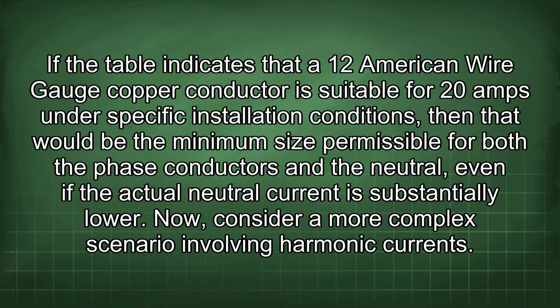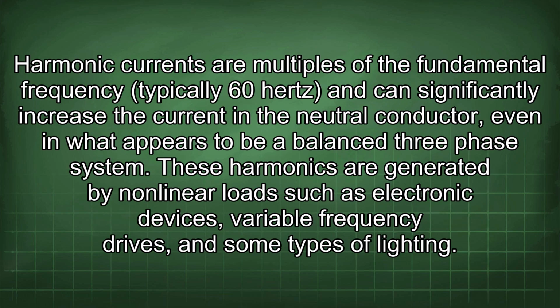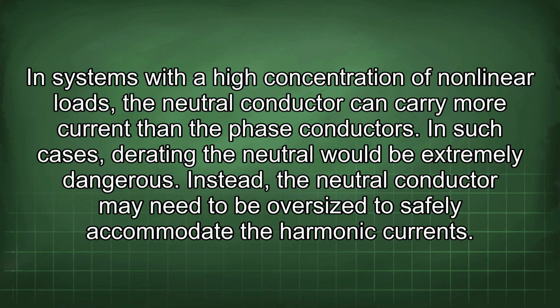Now, consider a more complex scenario involving harmonic currents. Harmonic currents are multiples of the fundamental frequency, typically 60 Hz, and can significantly increase the current in the neutral conductor, even in what appears to be a balanced 3-phase system. These harmonics are generated by nonlinear loads such as electronic devices, variable frequency drives, and some types of lighting. In systems with a high concentration of nonlinear loads, the neutral conductor can carry more current than the phase conductors.